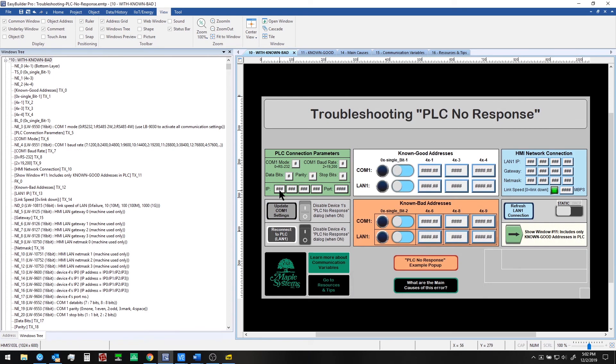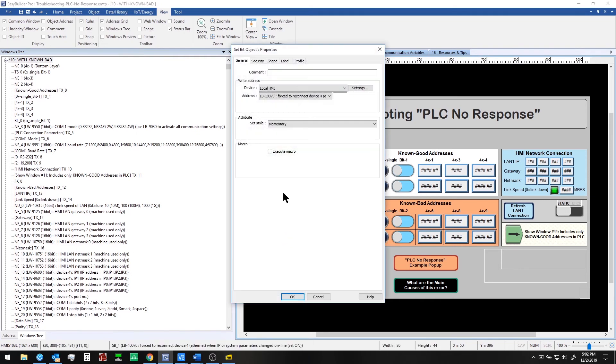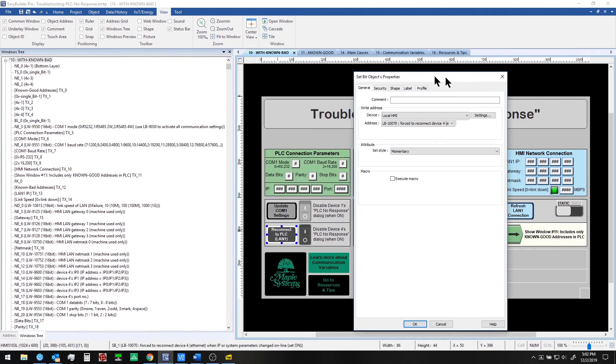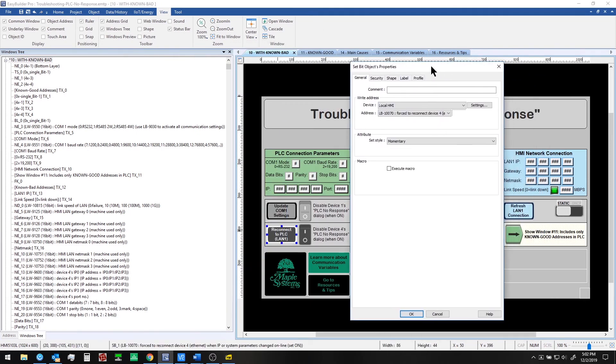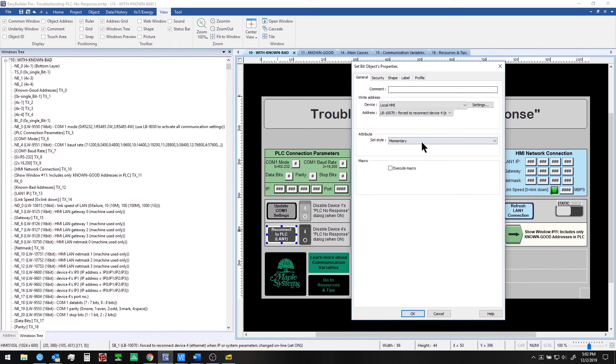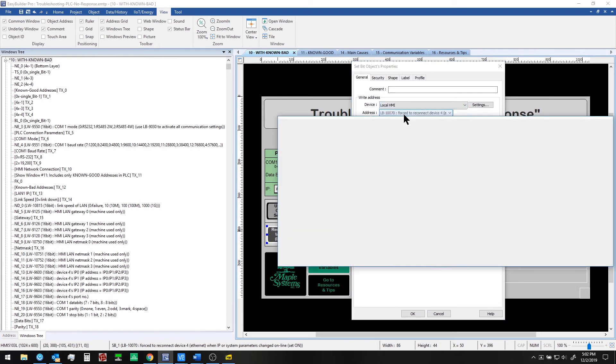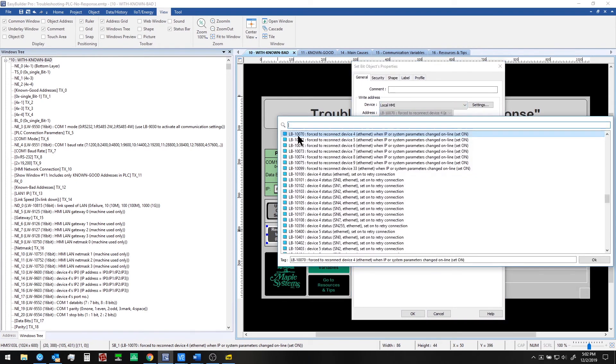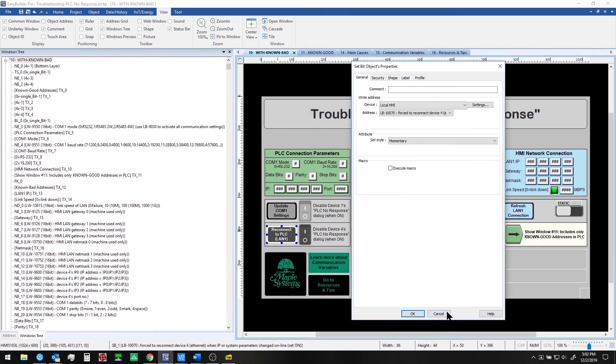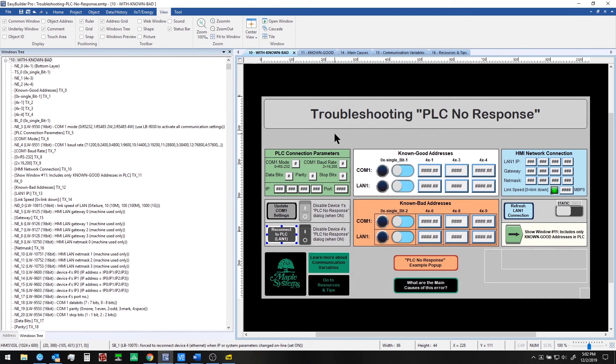If you change something about the ethernet communication parameters IP address or port then you'll need a similar function to apply the new settings for the interface. Here we're using local bit 10070 and this will force reconnection for device 4 ethernet when IP address or system parameters change online. So we set that on to update that connection.